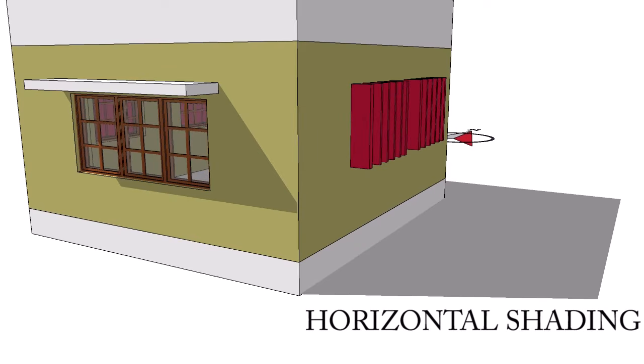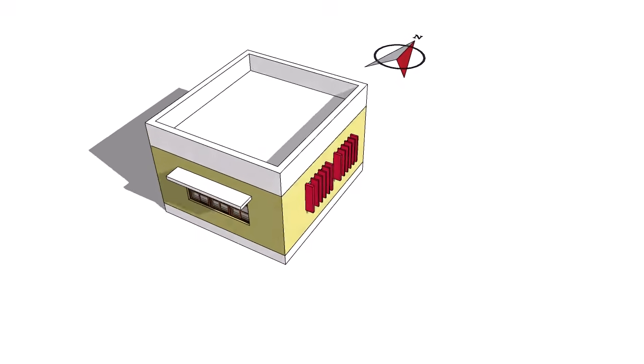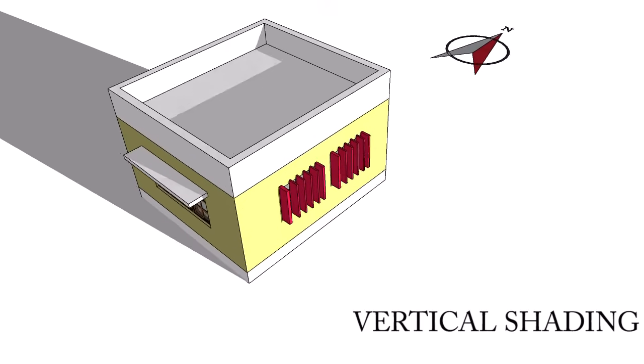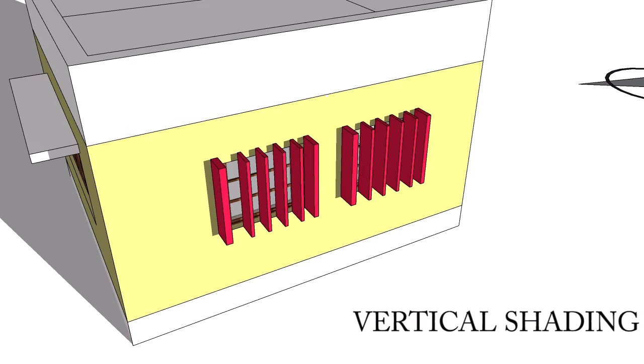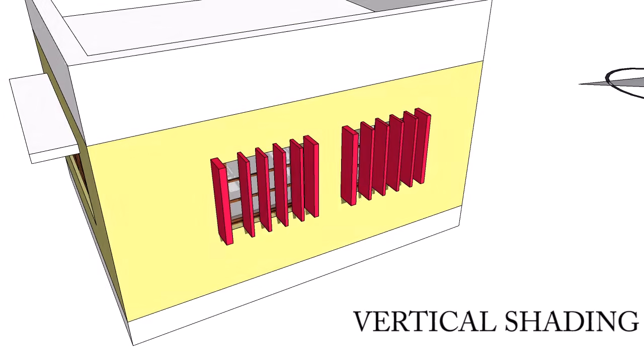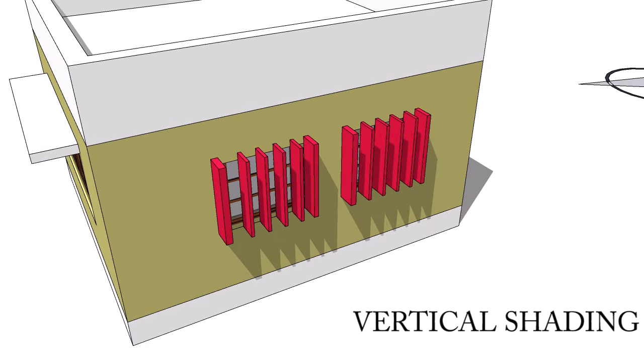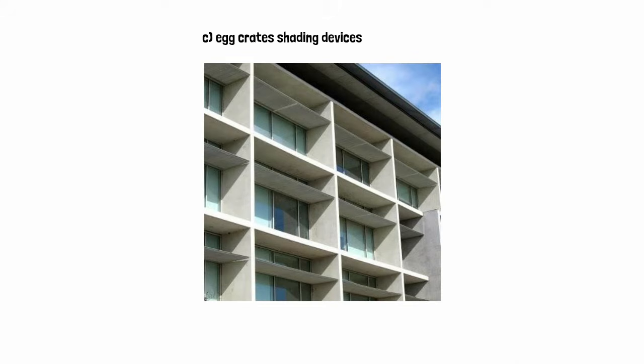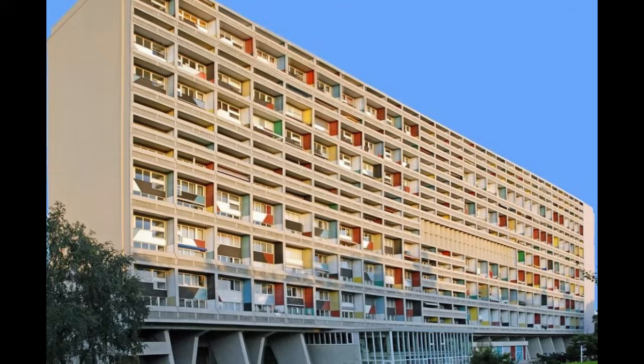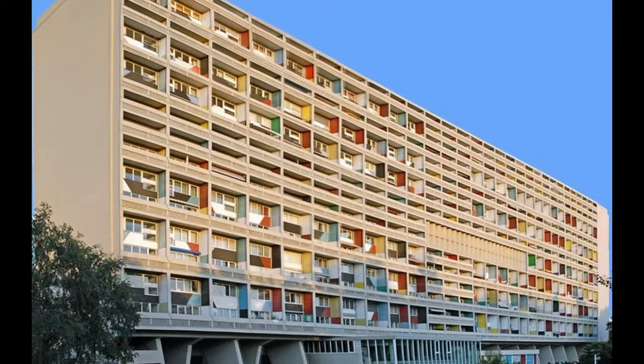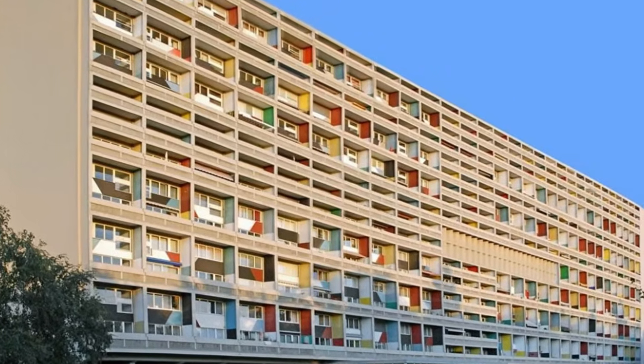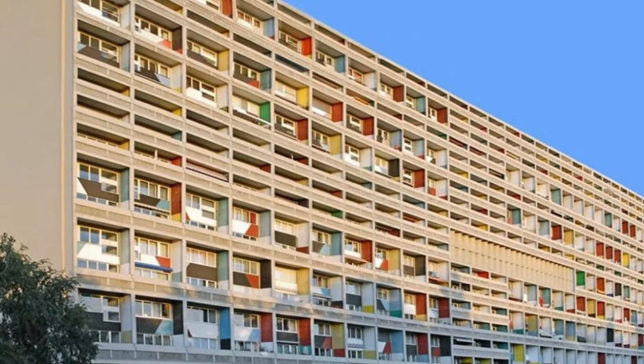There are three types of external shading devices: horizontal, vertical, and egg crate. Horizontal shading devices are used on the north and south faces of the building when the sun is at a high angle. Vertical shading devices consist of louver blades or projecting fins in a vertical position; this device is most effective when the sun is on one side elevation, such as eastern and western. Egg crate devices are a combination of horizontal and vertical elements and can be effective for any orientation depending on detail dimensions; they are suitable in hot climate areas.